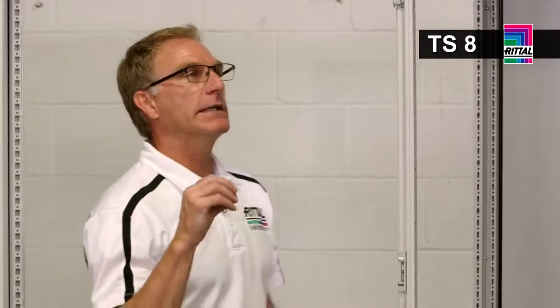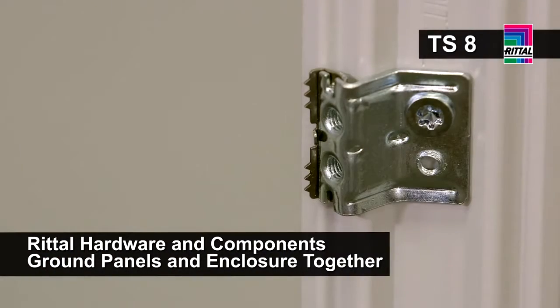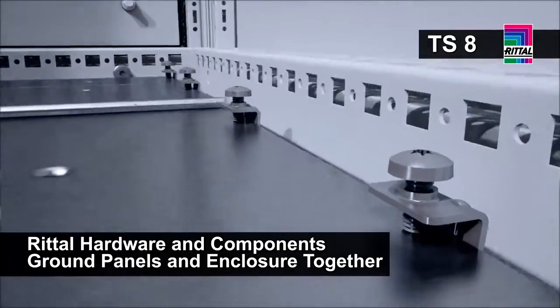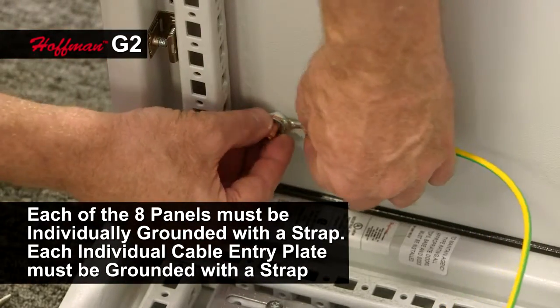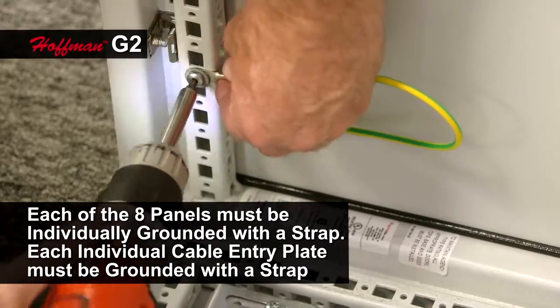One of the most important concerns for our customers is safety, achieved through best practices and proper bonding and grounding of electrical enclosures. In the TS8, the standard mounting hardware with its grounding teeth provides bonding back to the frame — even individual cable entry plates are each grounded back to the enclosure. With the G2, every individual panel, including each cable entry plate, has to have its own ground strap and associated hardware to provide the same protection level as the Rittal TS8.